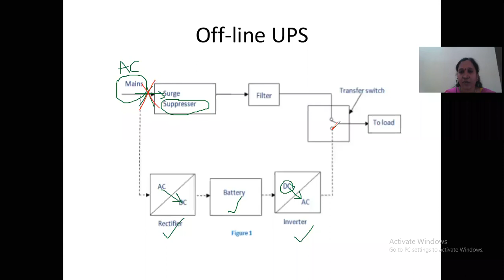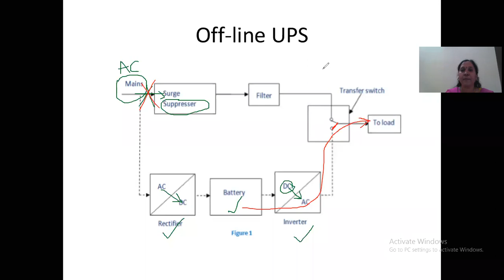This transfer switch is going to come into operation only when there is a power failure. Suppose there is a power failure, there is no power supply from here. Then what happens? This switch is to be switched in this way. Then this battery is going to give the supply via the switch. That is what happens in case of the offline UPS. We can call it a standby system.